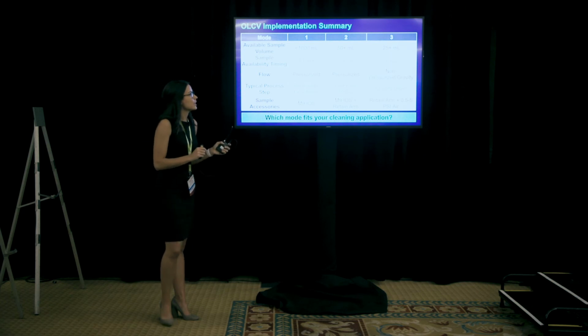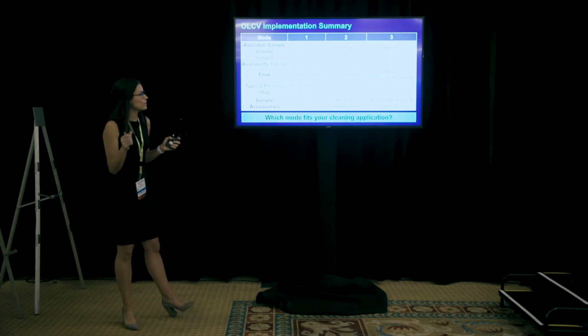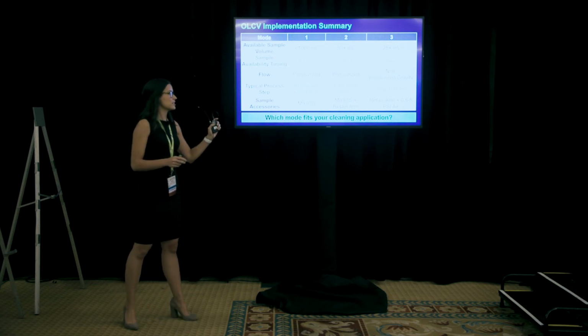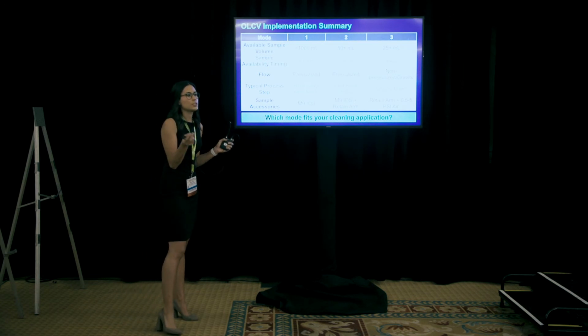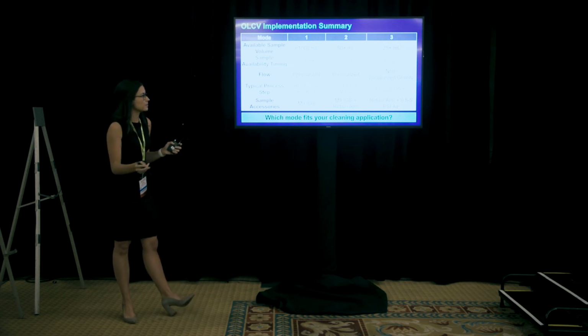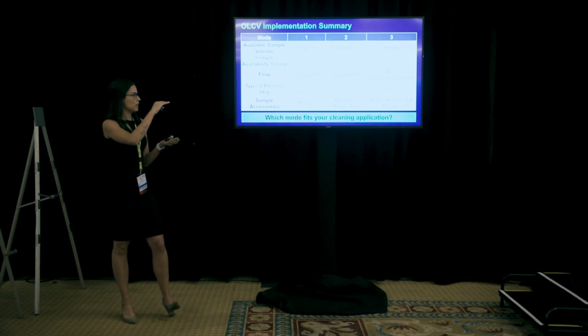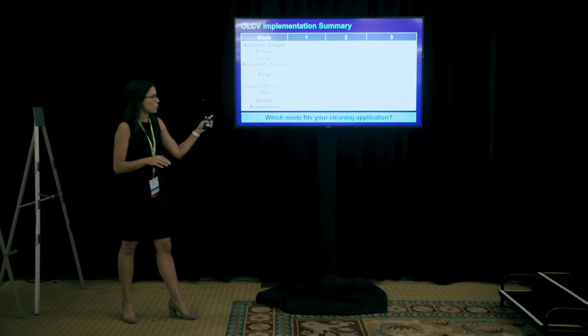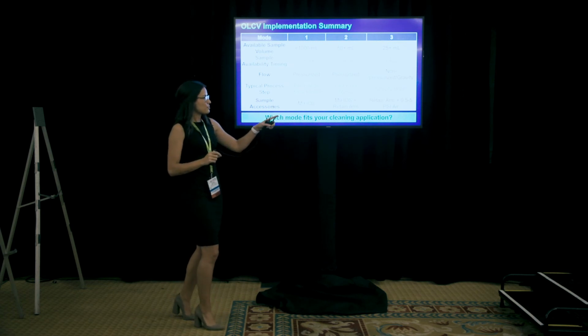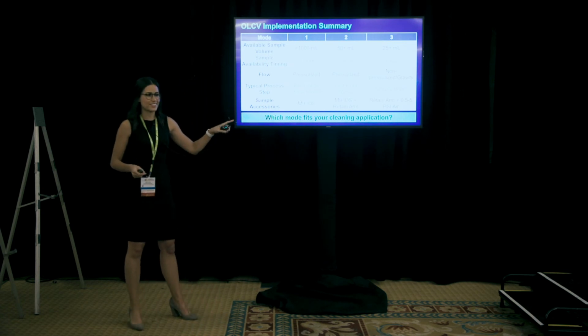Mode 2 is you have limited sample, you have limited time, but you do have a pressurized line. And the solution to this is what we're calling a retain arm. So you would have an inline retain arm, so you would avoid a dead leg. You would gather about 1,000 milliliters of your sample, and then you would be able to analyze it. So you overcome the time limitations. And then the third mode is gravity drain.